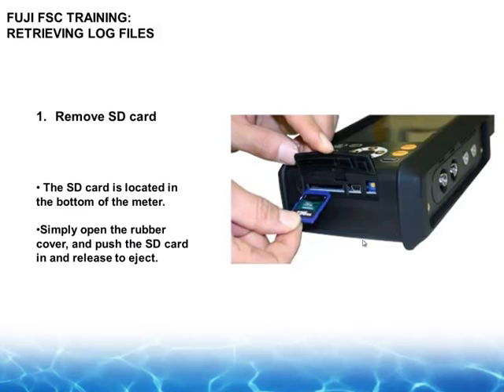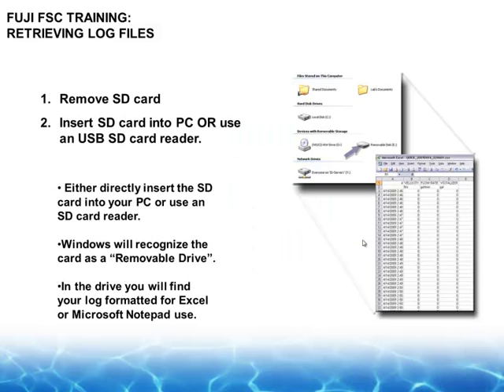And the way to get the data out is to remove the SD card. As I said, it also has a USB cable and software. Why bother? So here's the process. You take the SD card out of the flow meter. Boom. You stick it in your PC, your laptop, your computer, and if you don't have an SD port, we give you an SD to USB adapter, and if you lose it at Office Depot, it would probably cost you $7 to get a new one. You plug it in. You now turn on your computer, turn on Excel, and open the CSV file. No software required. Life is very simple.